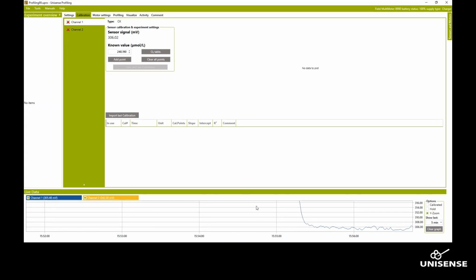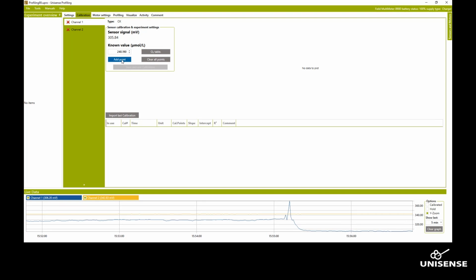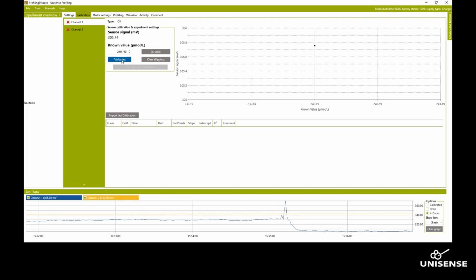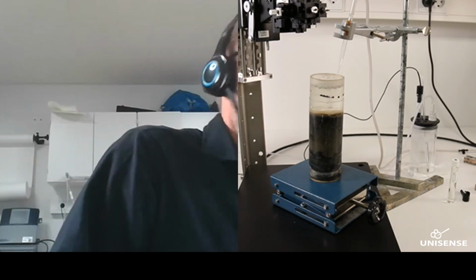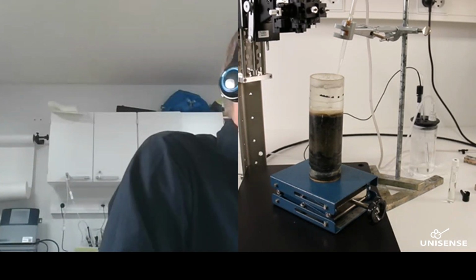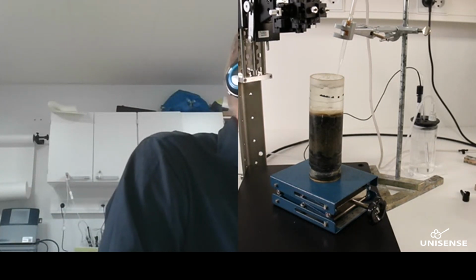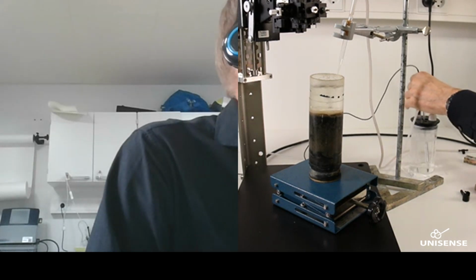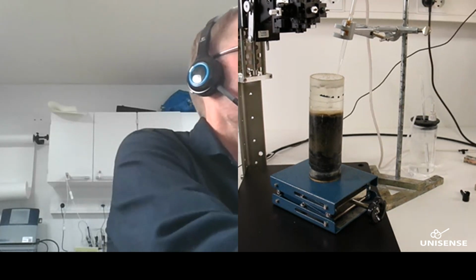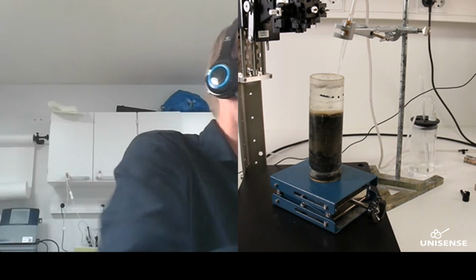So I'll just click add point, and now I have my calibration point for the known value. Then I need to make the zero calibration, and to do that I will just stop the screen sharing. So you should now be able to see the setup. I have this zero calibration solution which I will inject into the sensor. So I'll take the sensor from the calibration chamber and just mount it in a holder.